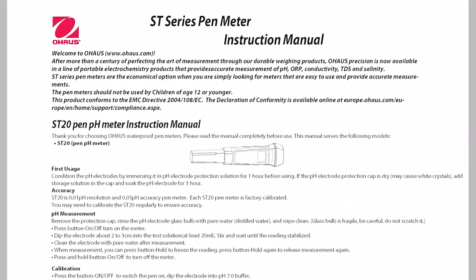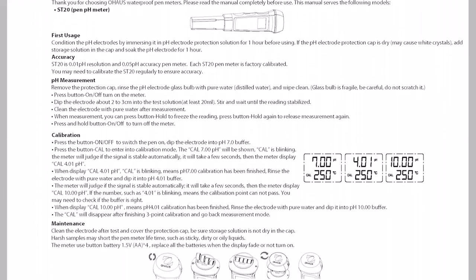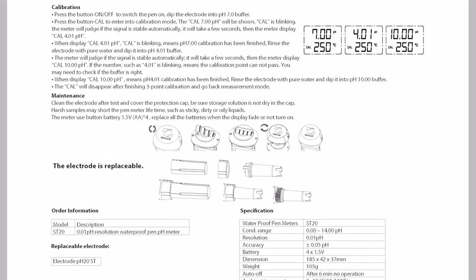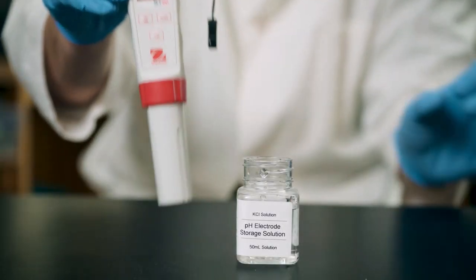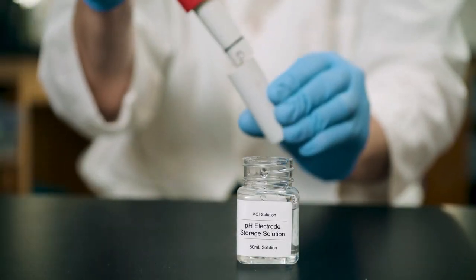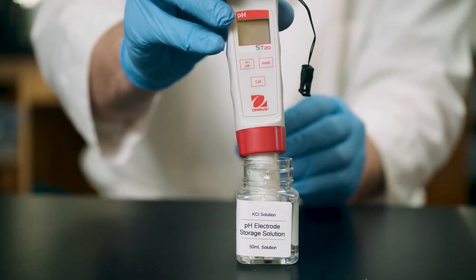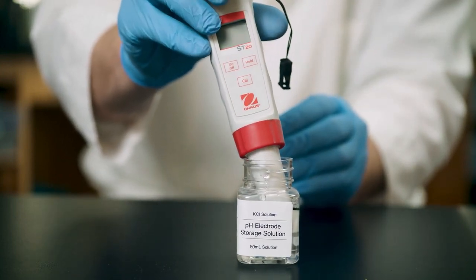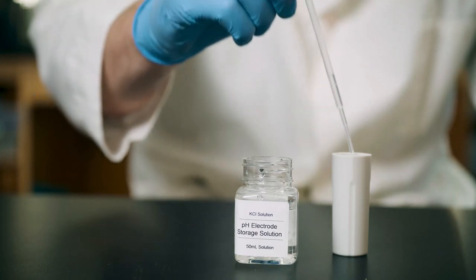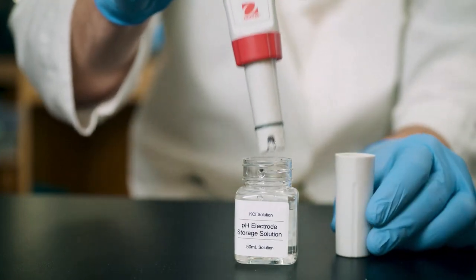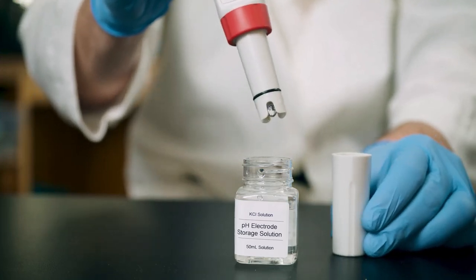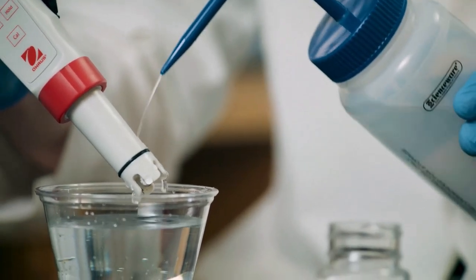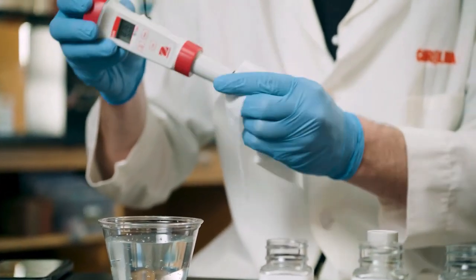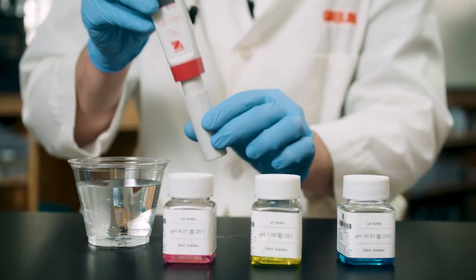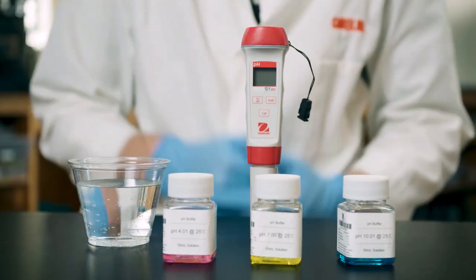Always read and refer to the instruction manual for operation, maintenance, and storage directions that are specific to your pH meter. When using a pH pen meter for the first time, condition the pH electrode by immersing it into pH electrode storage solution for 1 hour before using. If the electrode protection cap is dry, add storage solution in the cap and soak the pH electrode for 1 hour. Your pen meter is now ready for first-time use. Before and after using a pen meter to test a solution, rinse the pH electrodes with pure distilled water and wipe clean.